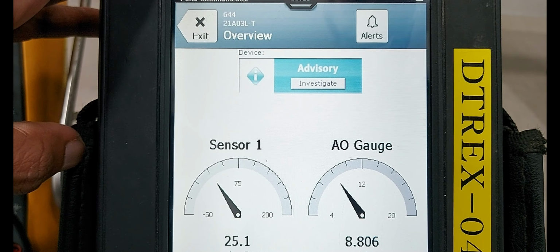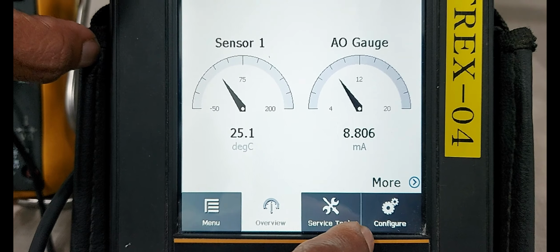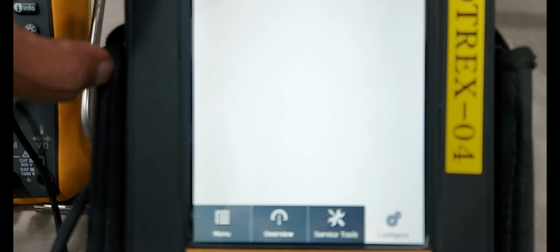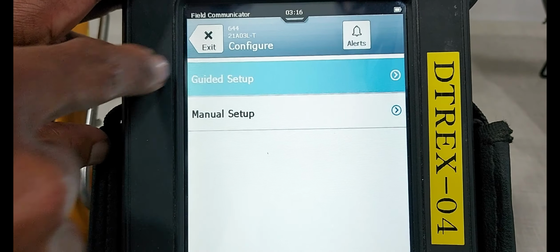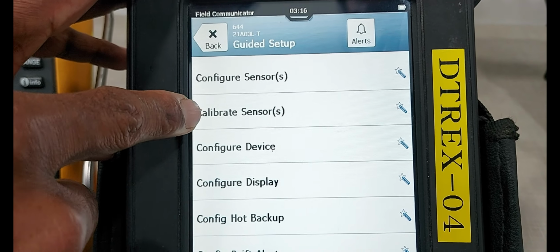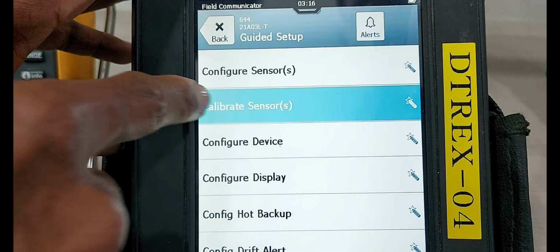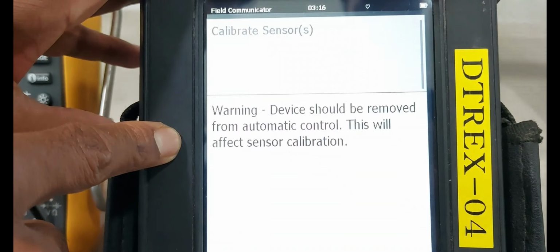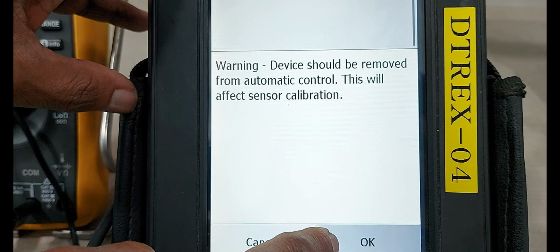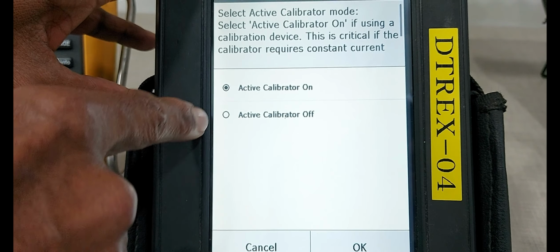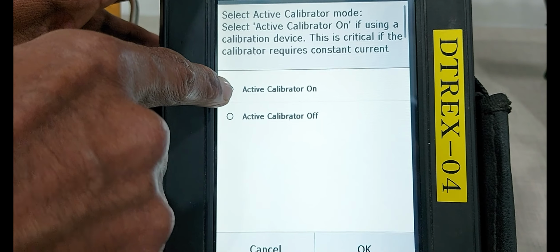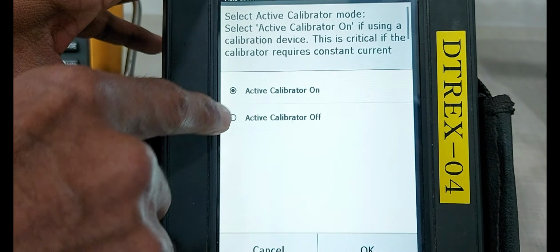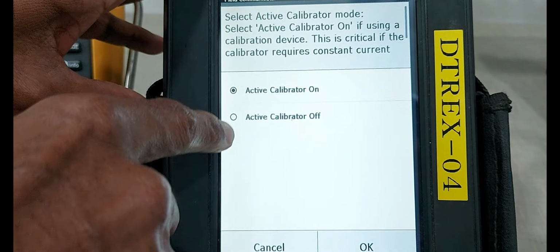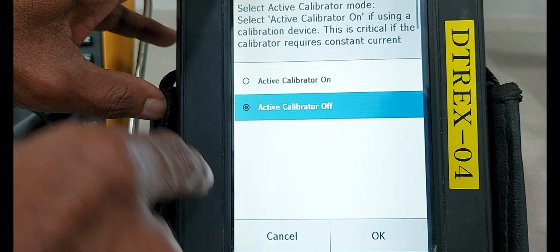Next we are doing the sensor calibrations. Select the configuration menu, guided setup, and the calibration of sensor, select it, okay. Active calibrator on, active calibrator off. We are normally using it for the normal condition, so okay.